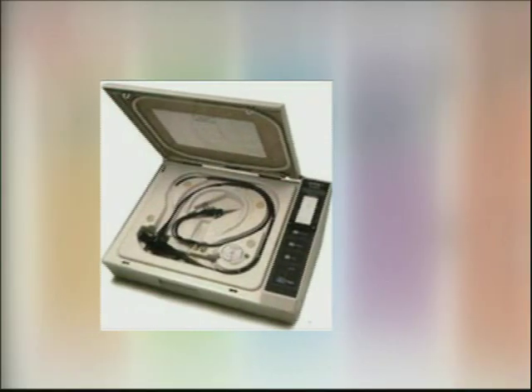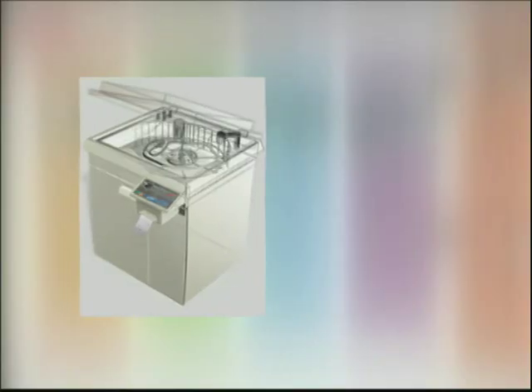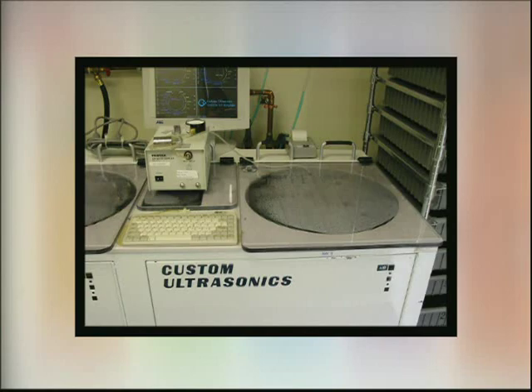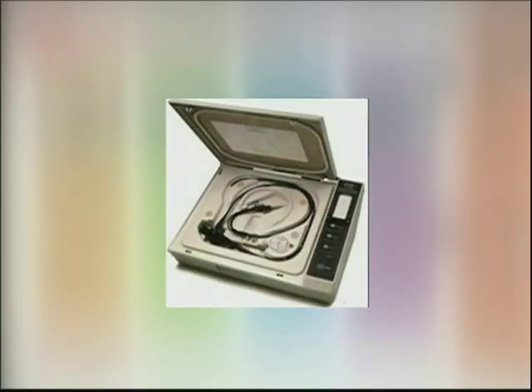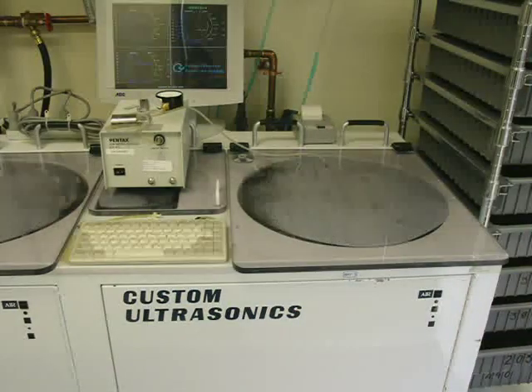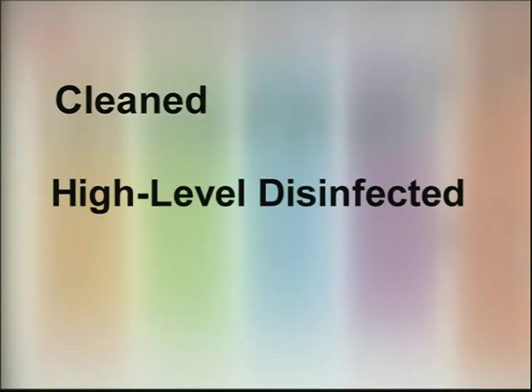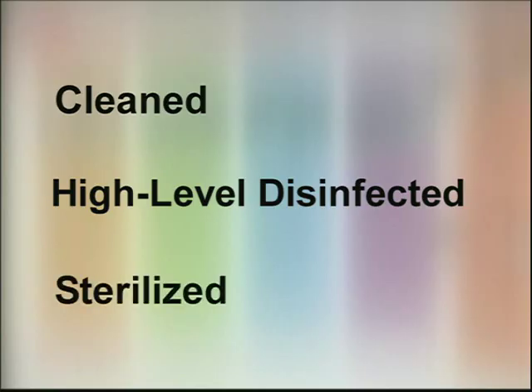AERs may provide a means of automated reprocessing of flexible endoscopes, including Pentax instruments. However, only those automated endoscope reprocessors should be used whose manufacturers provide device-specific instructions and have validation data, including simulated use studies that support each AER claim with respect to Pentax 70, 72, 70K, 72K series instruments. AER manufacturers should be consulted for their specific claims and written instructions for reprocessing Pentax products, including but not necessarily limited to the ability of the AER to provide a cleaned and high-level disinfected or sterilized endoscope and scope components, for example, valves. The identification of any special feature area or internal channel or scope component that cannot be reprocessed by the AER and therefore requires manual reprocessing.